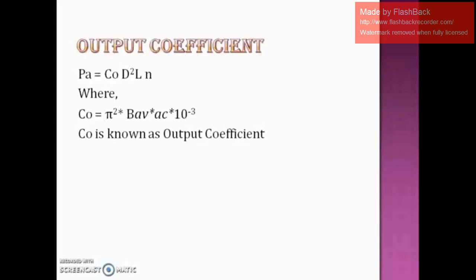The output equation is a very important relationship between the rating and main dimensions of the machine. For any given rating of machine, to start the design, we need to find the main dimensions. Interpreting our output equation: D² × L is the volume of the machine, and it is inversely proportional to speed as well as to the output coefficient.